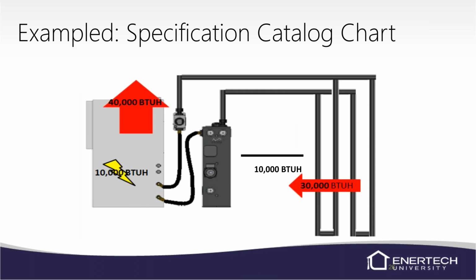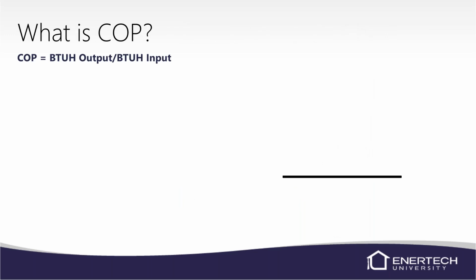What it is, is your total heating capacity divided by the energy it took to make that energy. So we have 10,000 BTUs that we use to make that energy, which would be our power input. So 10,000. And then we'd have our 40,000 BTUs to the home. So we'd take that 10,000, divide that into the 40,000, and that gives us a 4.0 coefficient of performance. In cooling mode, we use EER, energy efficiency ratio. In heating mode, we use coefficient of performance. Again, COP is BTU output divided by the BTU input. So what you're outputting to the home divided by what it took to make that.